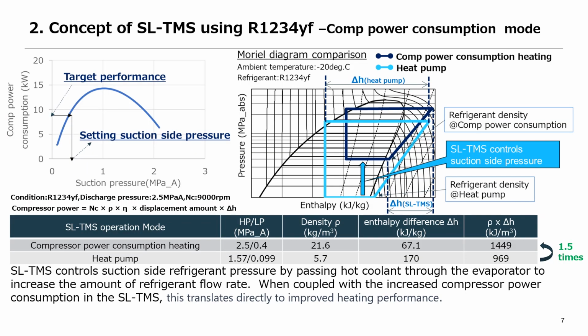Next, we'll be discussing the heating performance comparison between the compressor power consumption mode and the heat pump mode. On the left graph, the horizontal axis represents the low-side pressure, while the vertical axis indicates the compressor power consumption. Factors influencing compressor power consumption include the refrigerant type, compressor speed, refrigerant suction density, compressor efficiency, displacement amount, and refrigerant enthalpy, as illustrated by the blue line. Once we've determined the target heating performance, we can set both the required compressor power and the necessary low-side pressure.